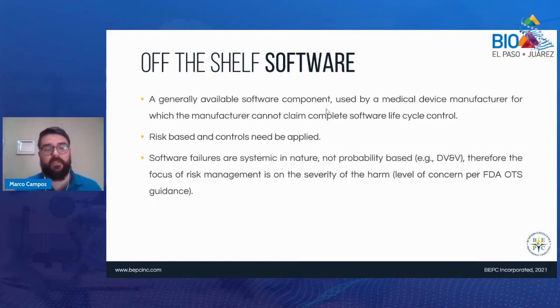But in a nutshell, what you need to be thinking about when doing your validation for your software is risk, and the controls that need to be applied to your validation. You have to think about this because any software failures that happen are systemic in nature. I don't want to delve into too many details, but if you think about validating and doing your DQ/IQ/OQ exercise, those failures are probability based, meaning there's a certain probability that event may happen. But in software, that's not necessarily the case. So your focus for validation needs to be on managing risk, or risk management, and you manage that by identifying the severity of harm of the potential failure of the software.